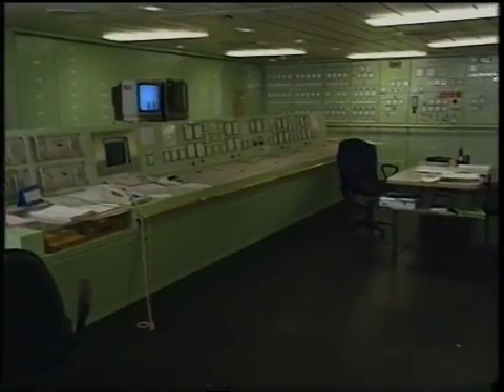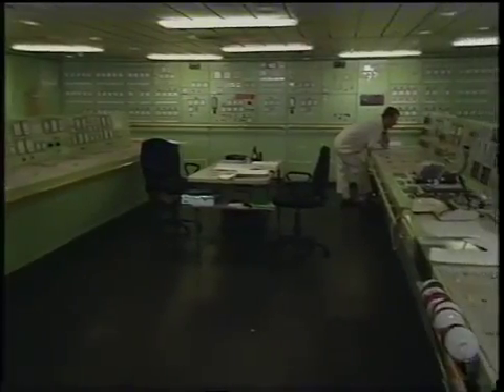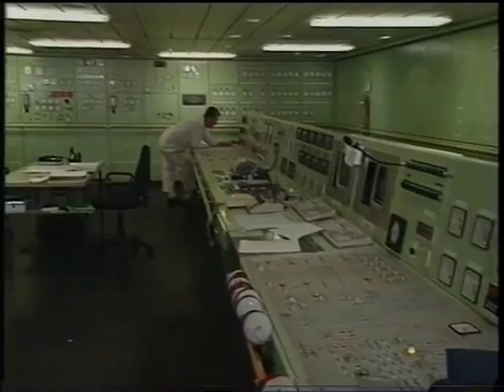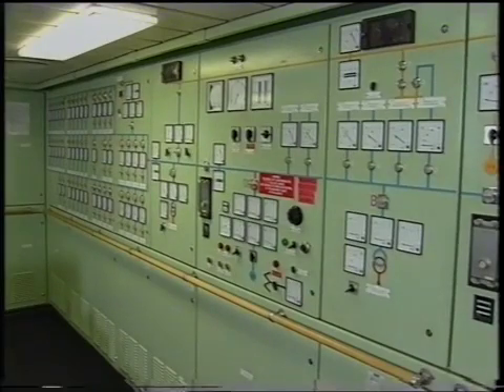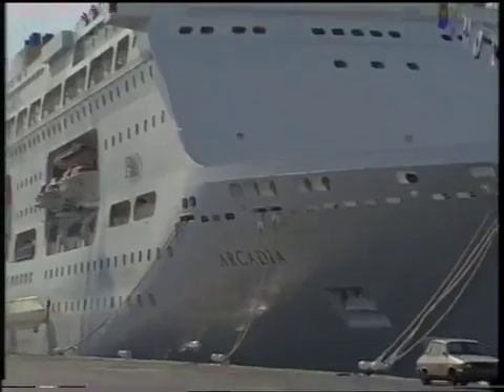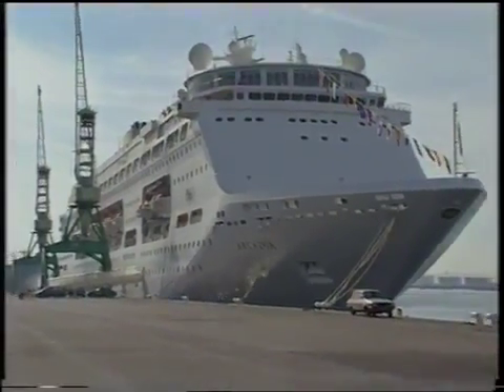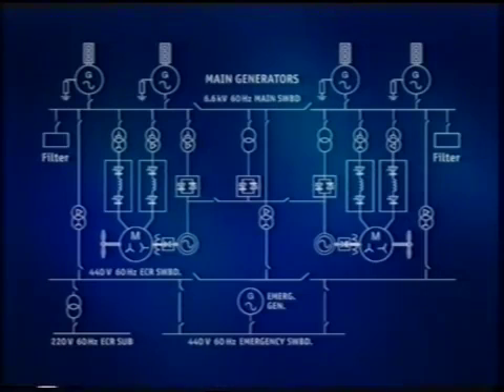A ship with such comprehensive requirements in effect houses a central power station which must be able to meet the varying demands whilst maintaining the supply voltage and frequency constant. So, in contrast to the average ship requirement of 1 to 3 megawatts, a modern cruise liner supporting comprehensive hotel facilities might require more than 40 megawatts. This necessitates high voltage power generation to reduce equipment size, current size and fault levels. Here the power is generated and distributed at 6.6 kilovolts, stepping down to 440 volts and 220 volts for auxiliary and support services. Some specialist vessels generate power at 11 kilovolts.